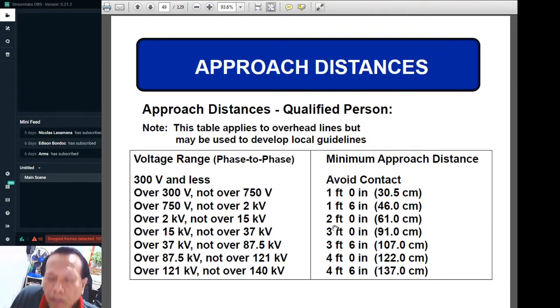So beware: if the high voltage line is close to your window, to your house, then you have to be very careful. You have to report this to the Meralco utility company so that they could do something to provide an insulator on that part of the line. So the higher the voltage, the farther the distance. Okay, that's only the minimum, so you are not supposed to get closer than that.